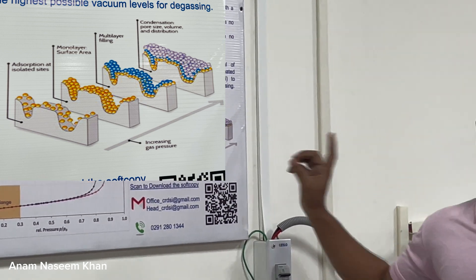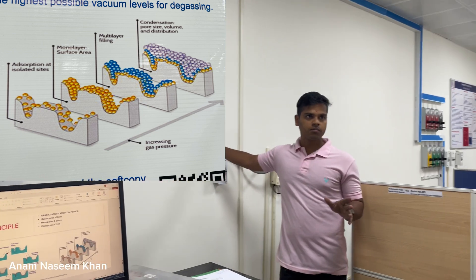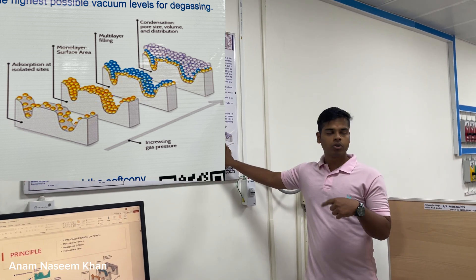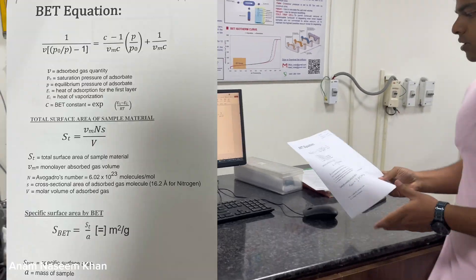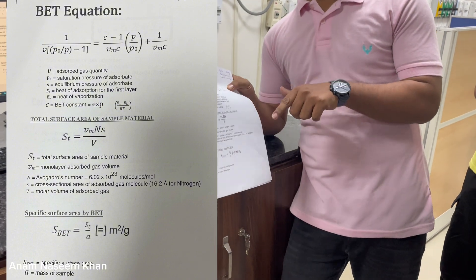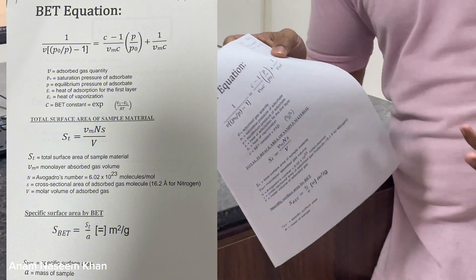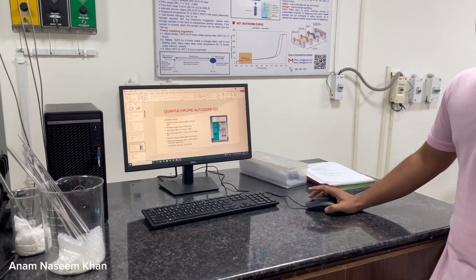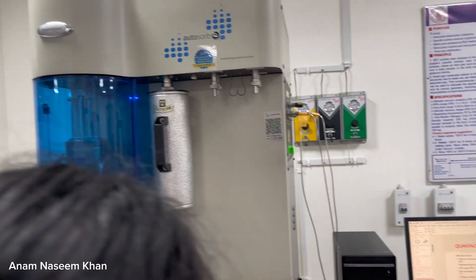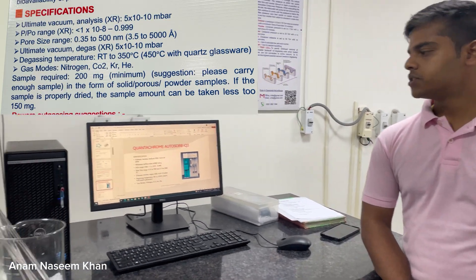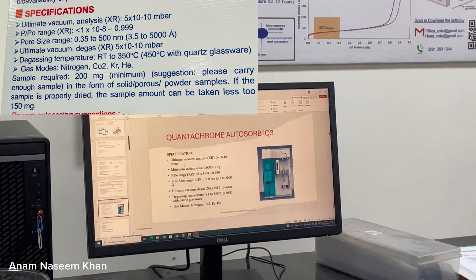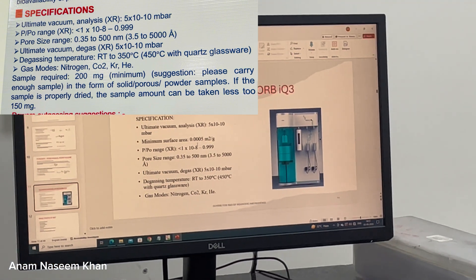In the case of chemisorption, there is no multilayer formation because only a chemical bond is formed, so only a monolayer is formed there. This is the BET equation — how we calculate pore size and surface area from the data. The measurable pore size range is 0.35 nanometers to 500 nanometers, and surface area greater than 0.0005 square meters per gram.